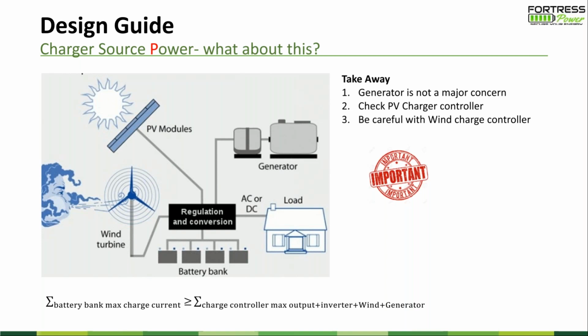I have one question here. Which type of breakers are the batteries using? Also, do you have a published time current curve for the breaker in order to check the inrush current? Yes, we do have that. The DC breaker is 125 amps, 250 amps, or 150 amps, three types based on the different products. And all of the inverter breakers are the delay version, not instantaneous trip. When we design the system, we fully test it. All of them handle short-term inrush current, at least for 20 milliseconds.